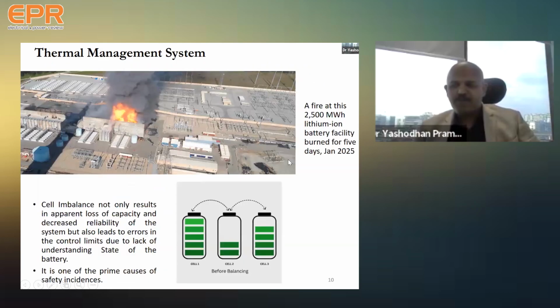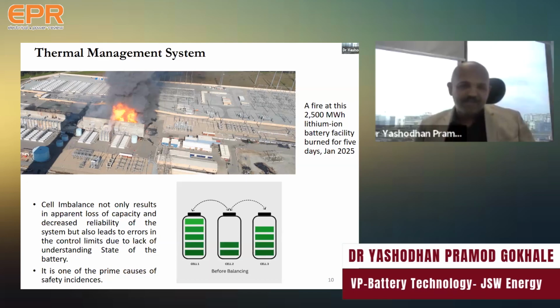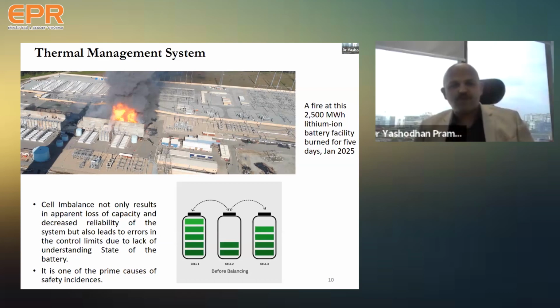Just to give you an example of the severity of how it can happen - there was one case in Europe where a 2.5 megawatt hour container caught fire, and it was burning for 5 days. There are various reasons - cheap quality cells because it's cheaper to mitigate tenders and so on. So cell imbalance - if in one batch there are say more than 5,000 cells, if a cell is imbalancing, it will cause loss in capacity, which leads to control limits that you put on the BMS.